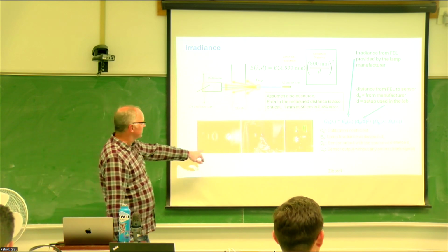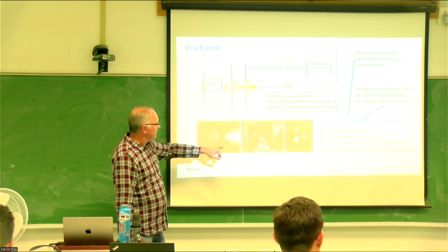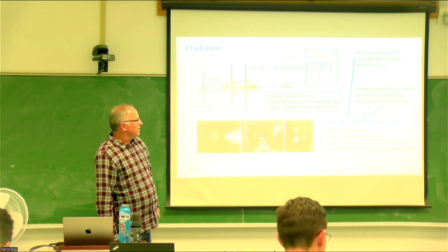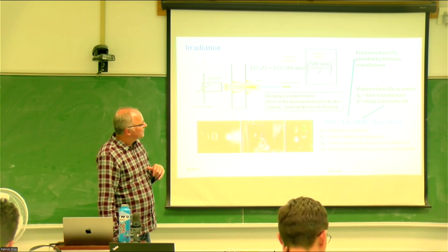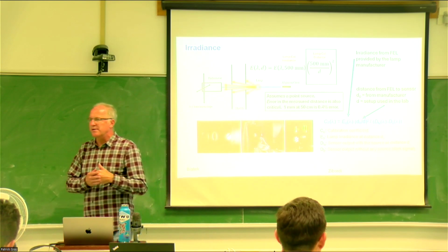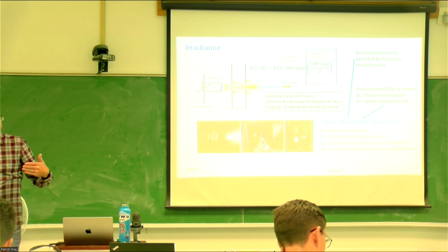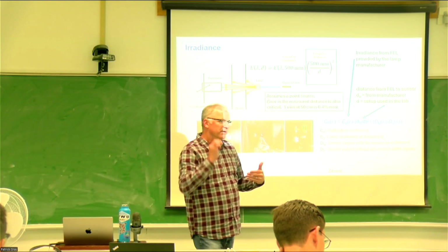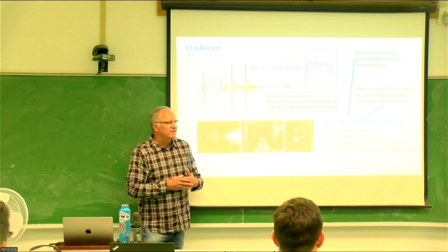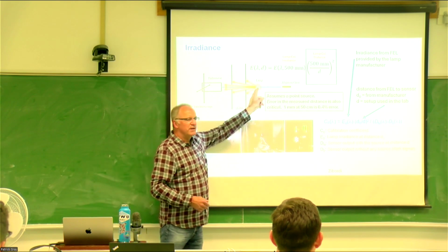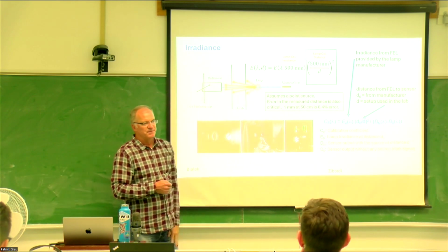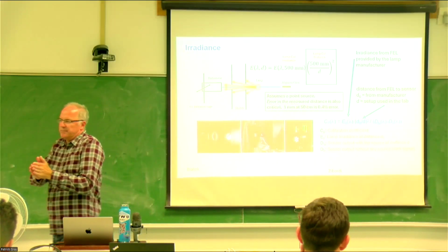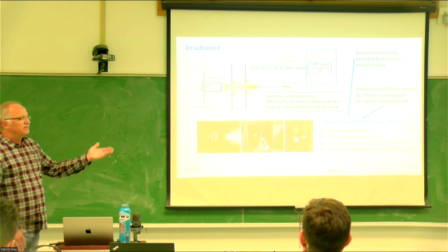These are some pictures of that. Here's that aperture shield that opens up. There's another one, the radiant sensor, the 7-channel radiant sensor. So we also learned when I went over this, what does the radiance do with distance away from your point source? The intensity decreases. By what factor? One over the square of the distance between your lamp and whatever target you're measuring. So those FEL lamps that we buy, they're all calibrated at some set distance. In this case, it's usually 50 centimeters.